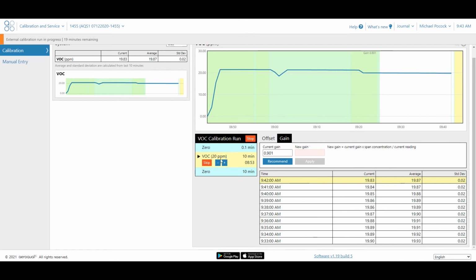So 5% of 20 ppm is 1 ppm. So for this calibration, as long as we are between 19 and 21, so 20 plus or minus 1 ppm, 19 to 21 ppm, we don't have to make any changes at all. We've got a very stable reading.